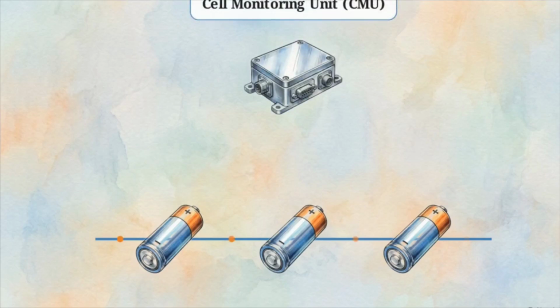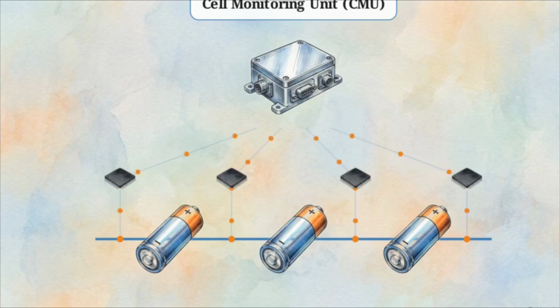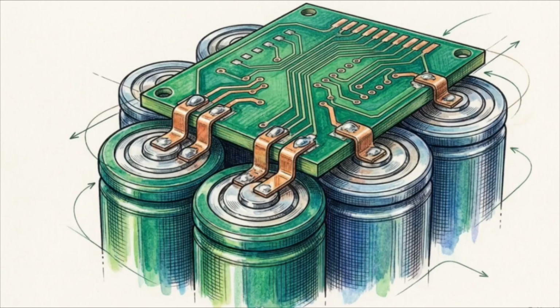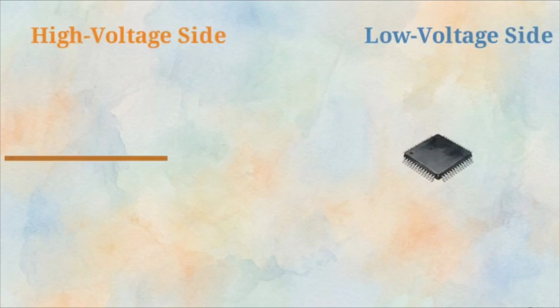The CMU relies on specialized analog front-end integrated circuits. These chips attach directly between the individual cells to pull continuous, highly accurate voltage and temperature readings. Because analog signals degrade over distance, these circuits must be physically mounted as close to the battery cells as possible to ensure the data is pristine. This proximity creates an engineering hazard.